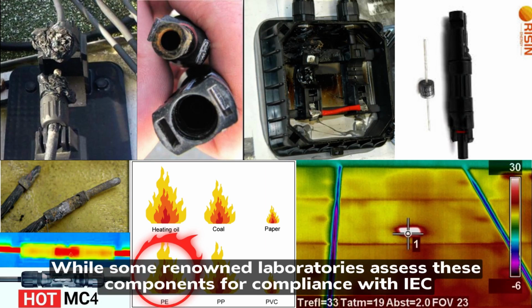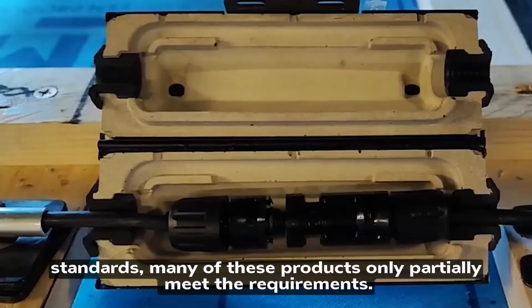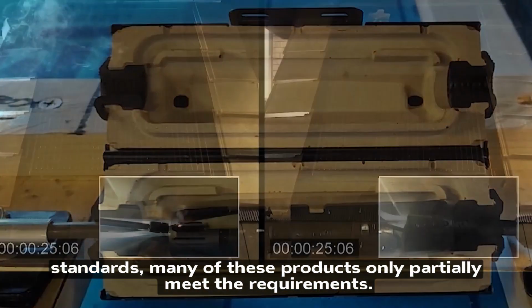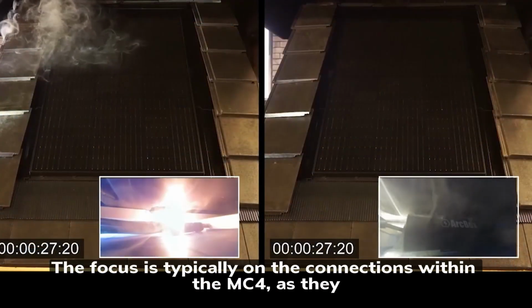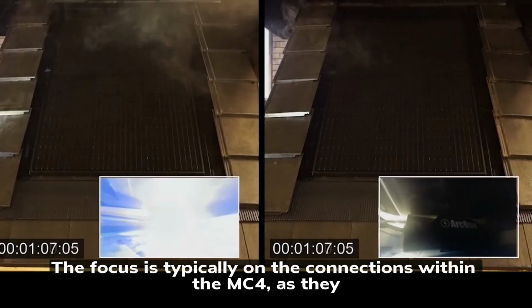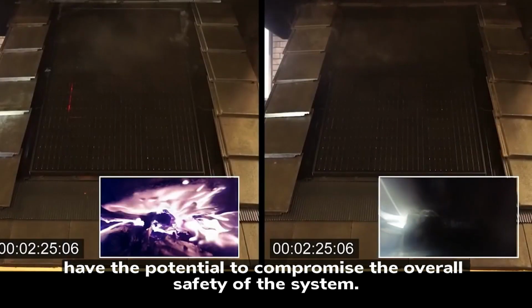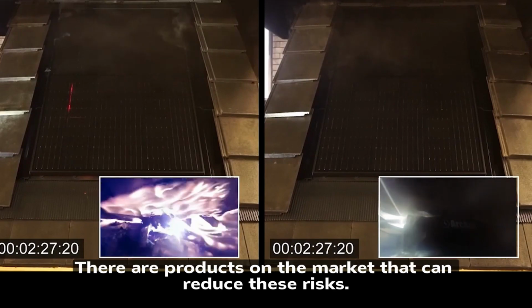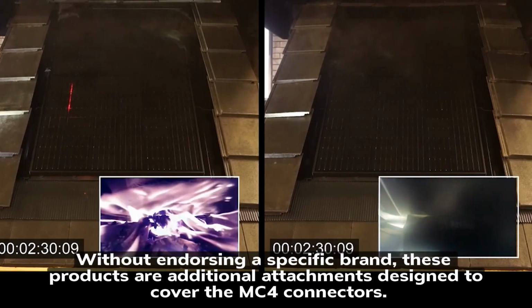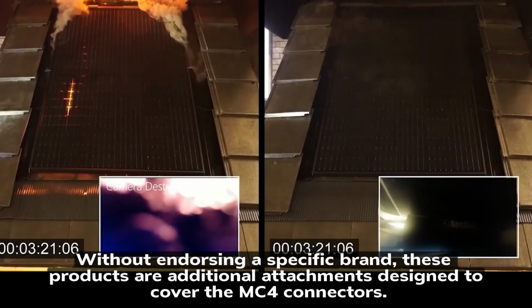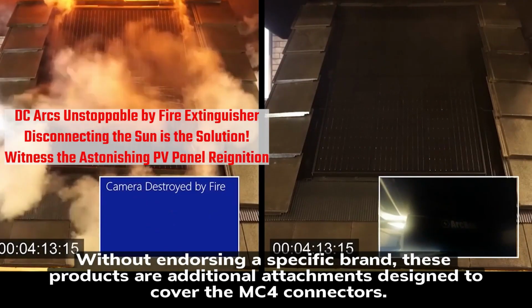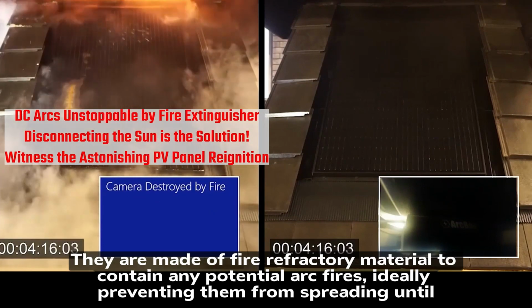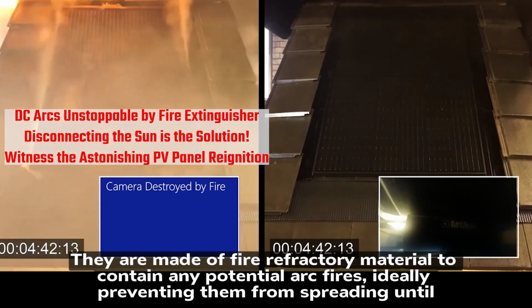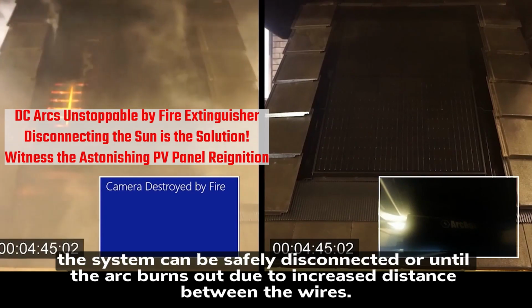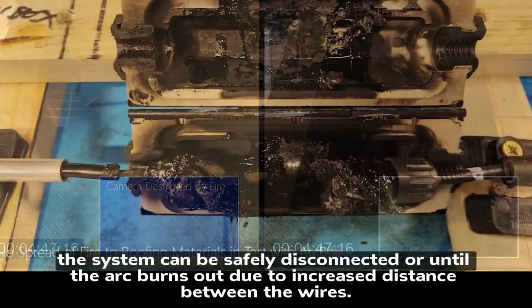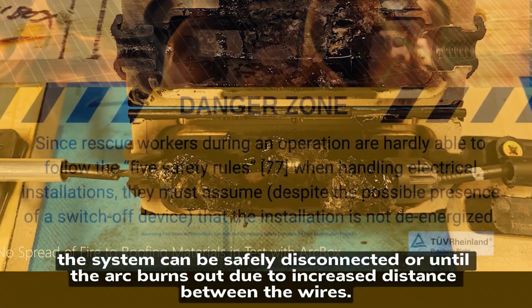While some renowned laboratories assess these components for compliance with IEC standards, many of these products only partially meet the requirements. The focus is typically on the connections within the MC4, as they have the potential to compromise the overall safety of the system. There are products on the market that can reduce these risks. Without endorsing a specific brand, these products are additional attachments designed to cover the MC4 connectors. They are made of fire-refractory material to contain any potential arc fires, ideally preventing them from spreading until the system can be safely disconnected or until the arc burns out due to increased distance between the wires.